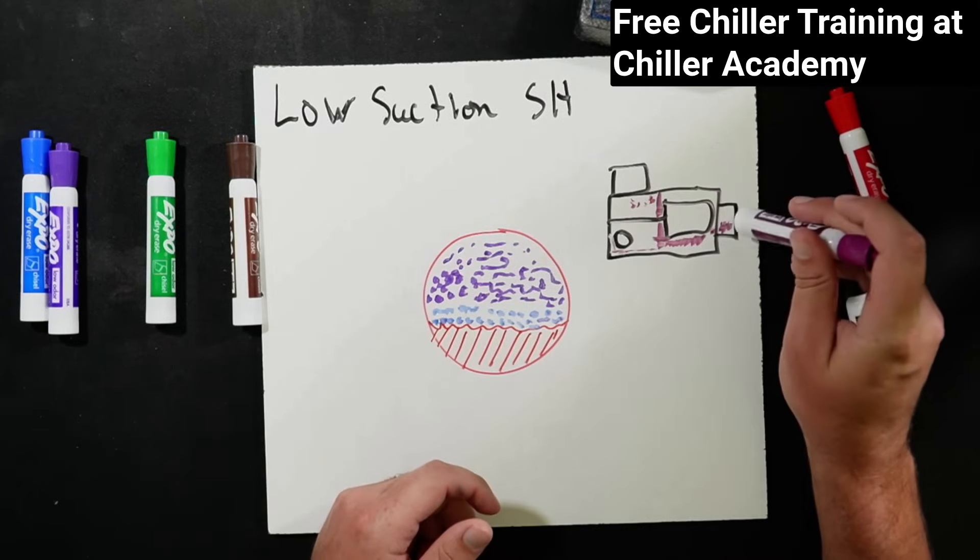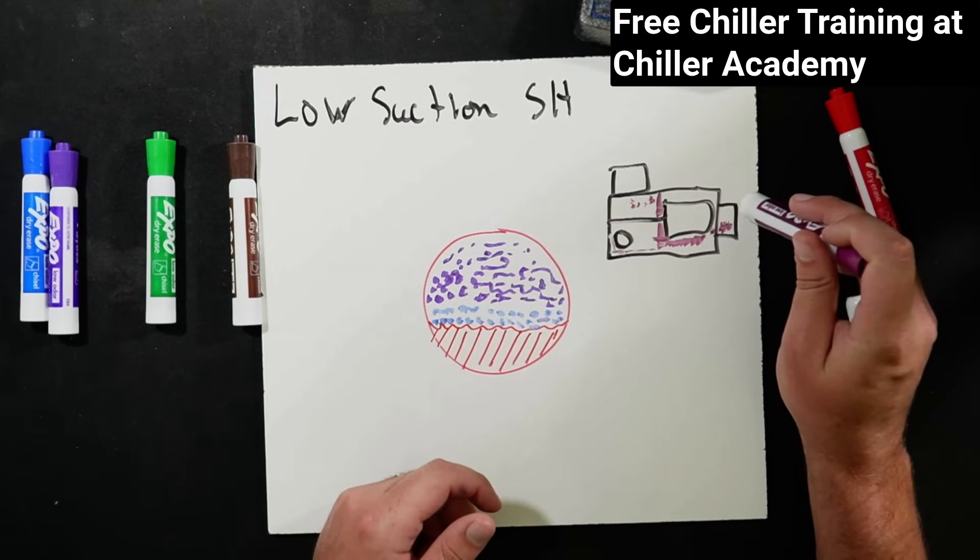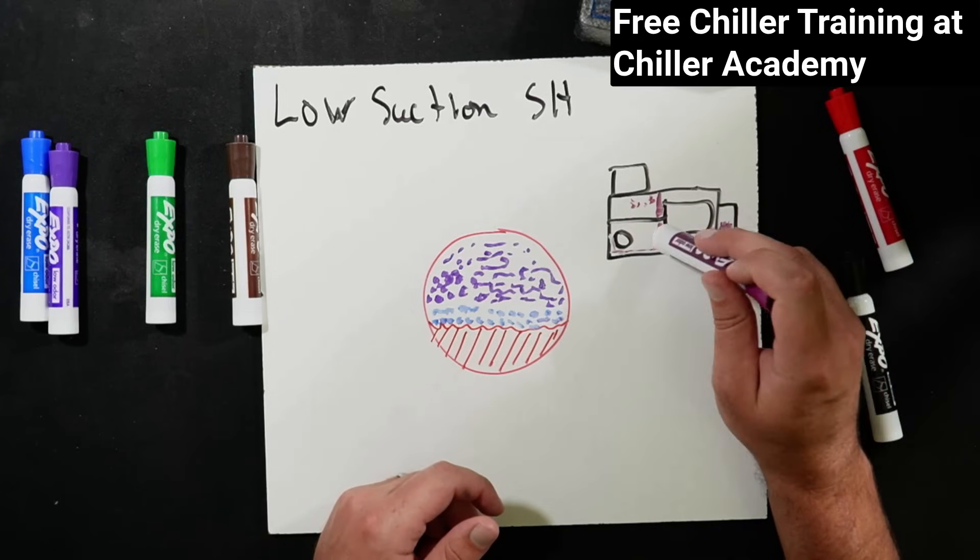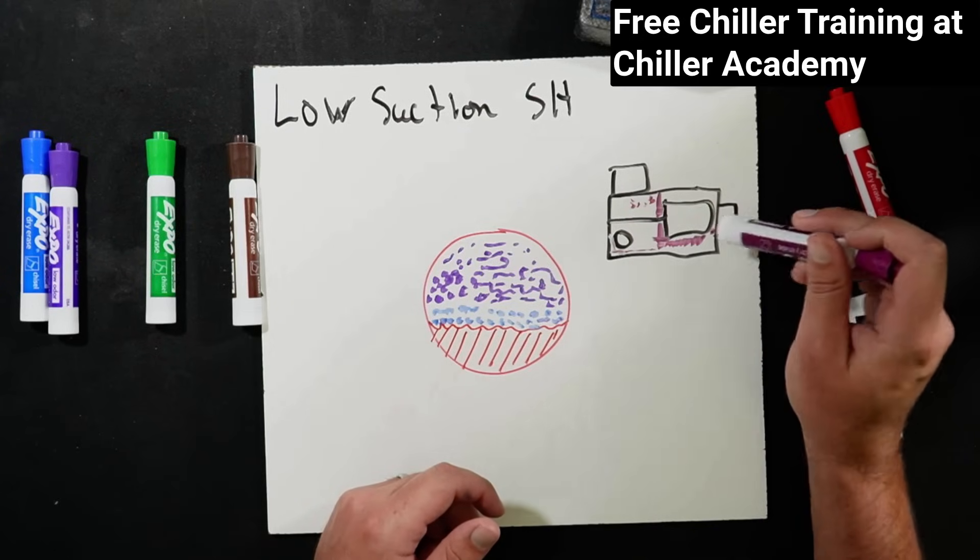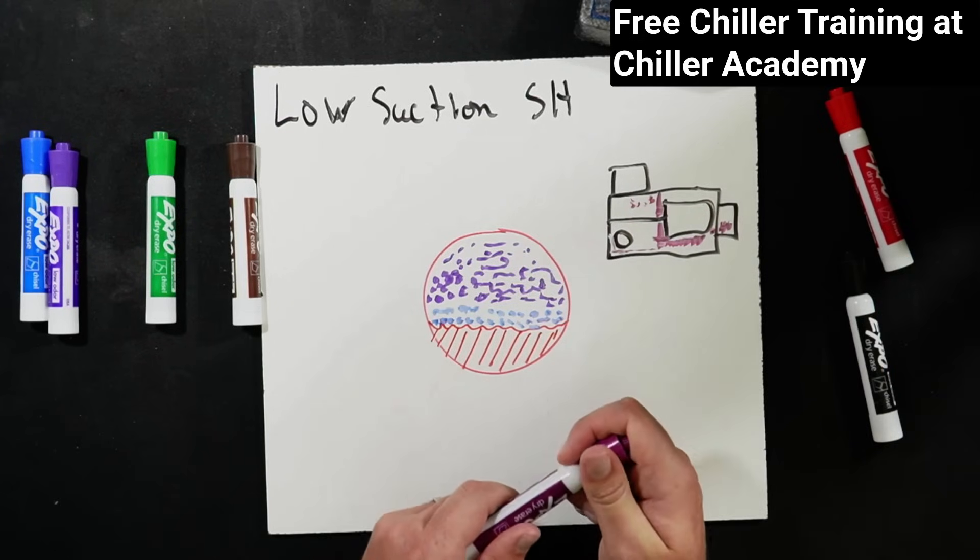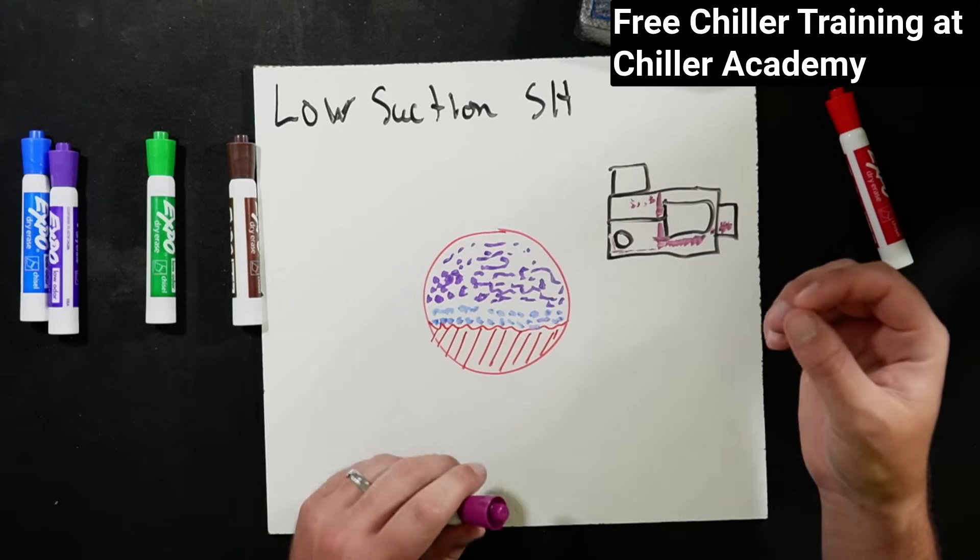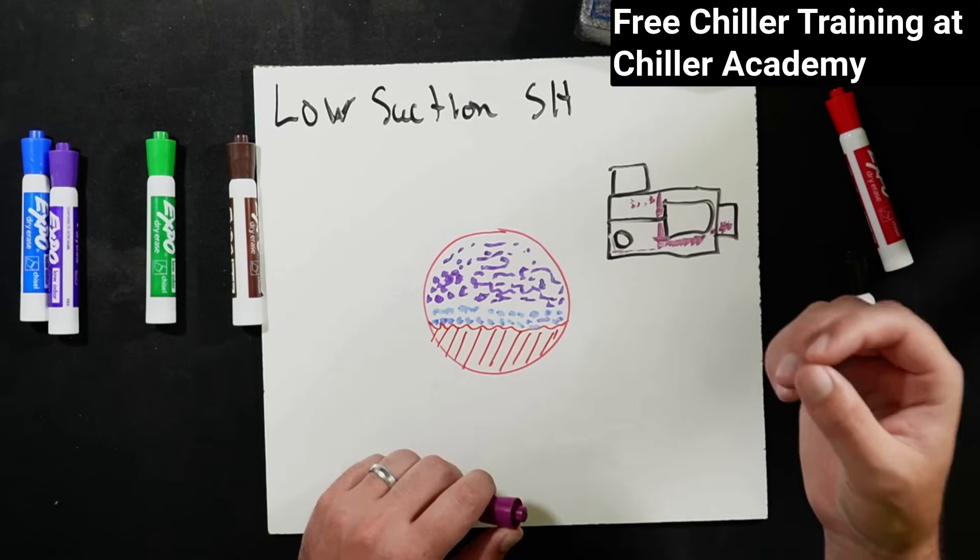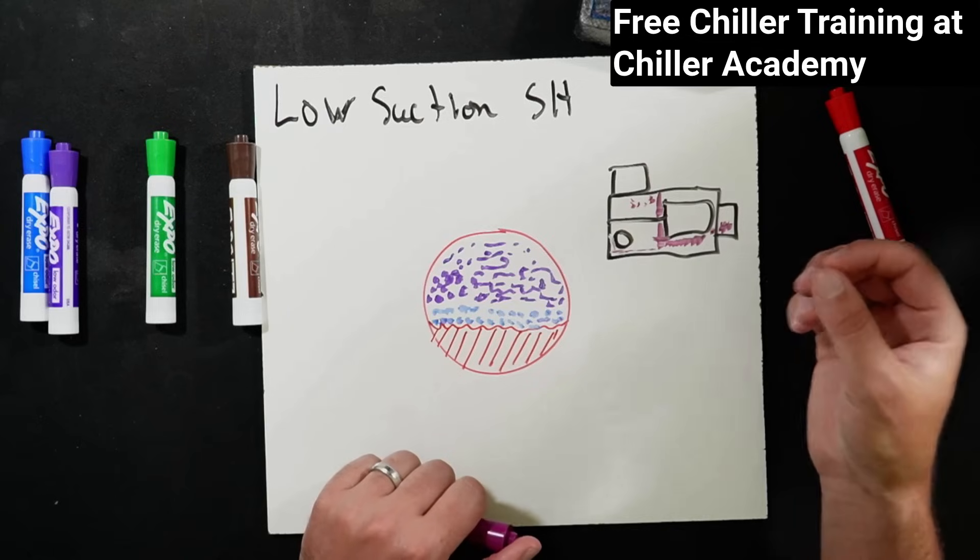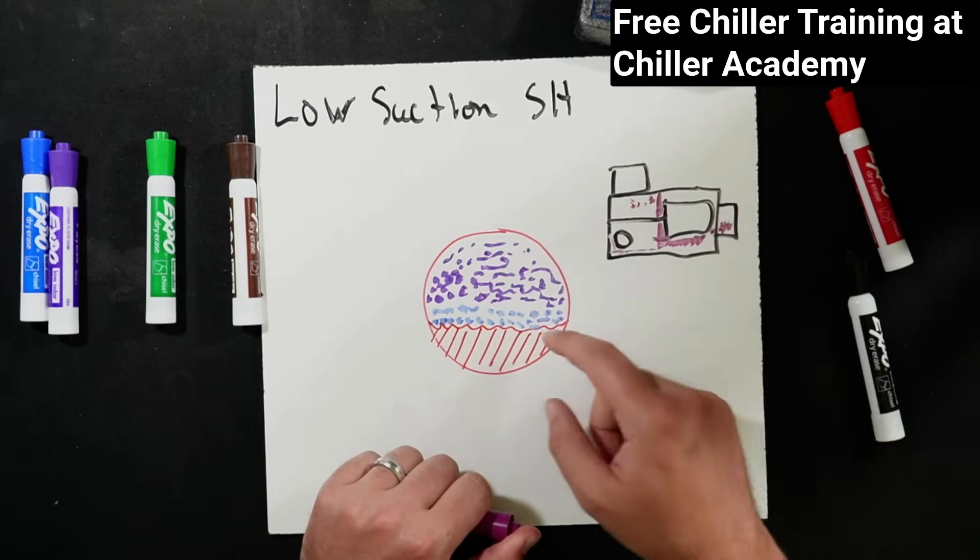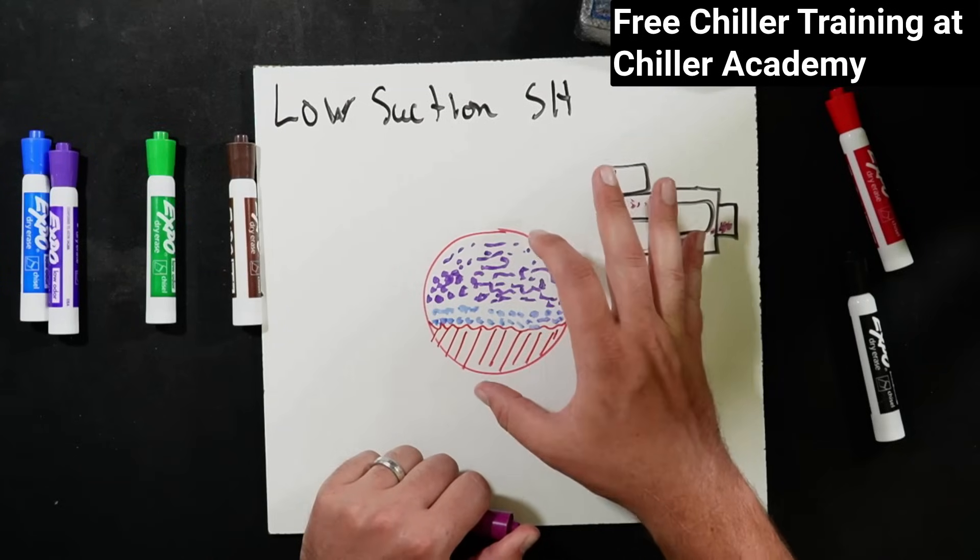And it actually doesn't take that much. You could have a fairly minor flooding action where we're not just hardcore flooding this compressor out, but it's just a very small amount coming in. It's not a fully saturated vapor refrigerant coming back into our compressor. When that happens, we will foam. So this is evidence of that.